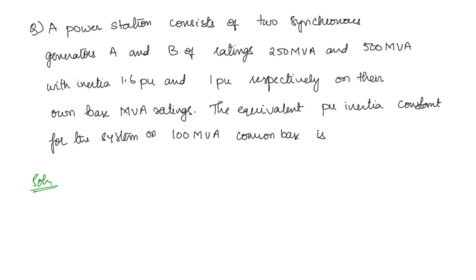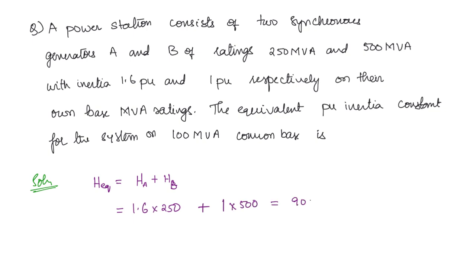Since it is not stated whether the machines are coherent or non-coherent, we take them as coherent. For coherent machines, the equivalent inertia constant is just the addition of individual inertia constants. The inertia constants are given in per unit with their base ratings. The actual value is: (1.6 × 250) + (1 × 500) = 400 + 500 = 900 MVA.